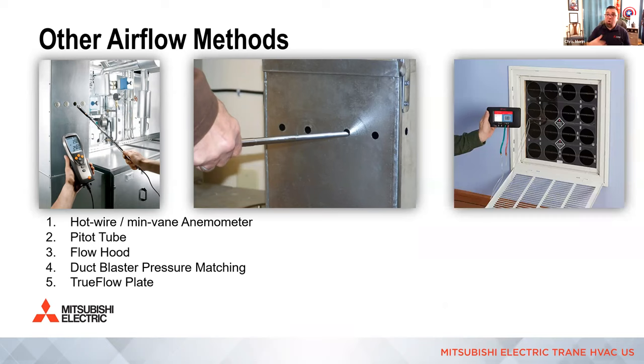And then the last one, which is the one I personally love because it's so repeatable and I always get the same number and it's quick, is using a TrueFlow plate from the Energy Conservatory. There's little plates. As long as you can slide this in a central return, either at the furnace or air handler, you're able to do a cross section of the duct with velocity pressure. The meter will actually change it right over to CFM for you. Or you can take a dual input manometer and convert pressure to CFM on their chart. So those are the approved methods from ACCA, quality installation, and the Energy Star checklist. Those are the ones you could use to measure volume of air.